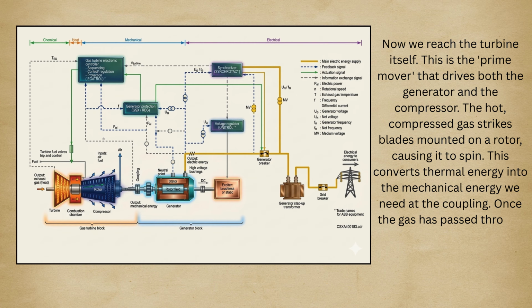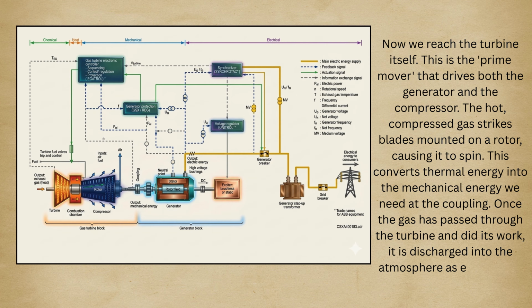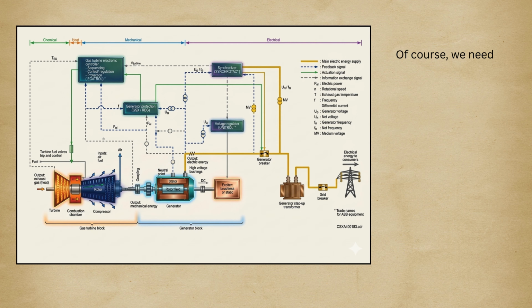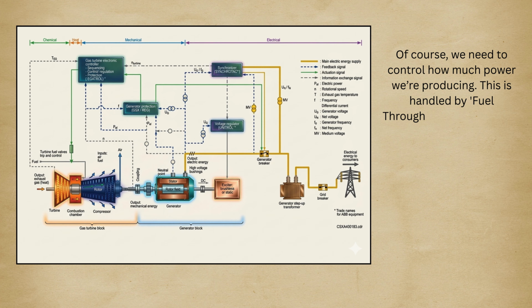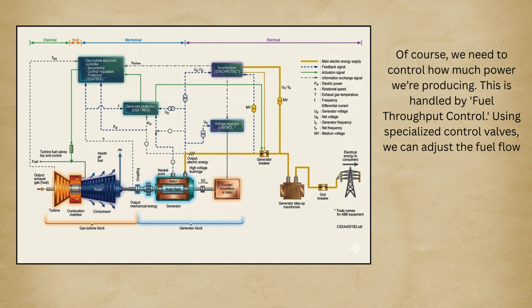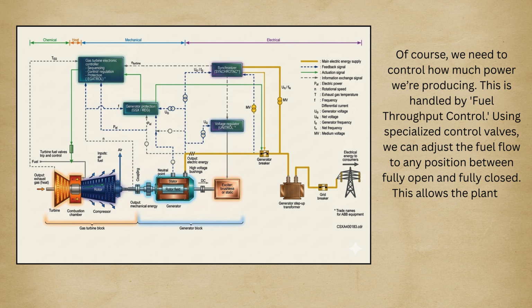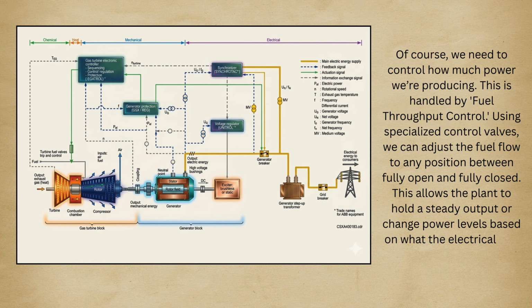Once the gas has passed through the turbine and done its work, it is discharged into the atmosphere as exhaust gas. Of course, we need to control how much power we're producing. This is handled by fuel throughput control. Using specialized control valves, we can adjust the fuel flow to any position between fully open and fully closed. This allows the plant to hold a steady output or change power levels based on what the electrical grid needs.